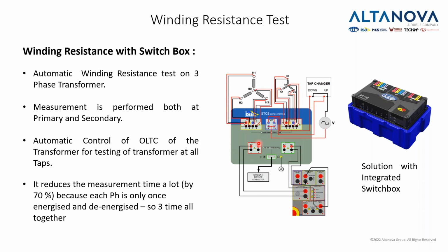So single phase or with a switch box. Once again, we can use an M7, which has an integrated switch box, or STS, which has an external switch box, because the switch box will make testing 60 to 70% faster. The reason is that when we use a switch box, we need to energize each phase only once and de-energize only once. And if we don't have this, we need to energize and de-energize for each position of the tap changer. So if we have 20 positions of the tap changer, there is a big difference between 3 energizations and 3 de-energizations, and between 60 energizations and 60 de-energizations. So in that respect, if I can suggest, always go for an automatic device with a switch box.